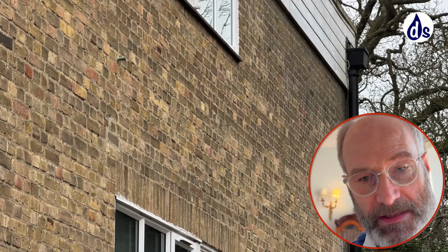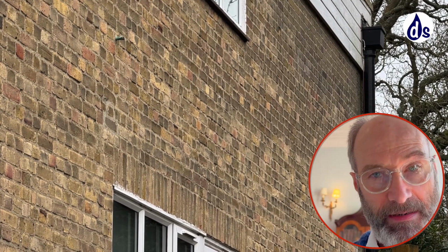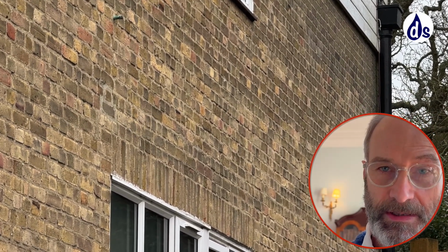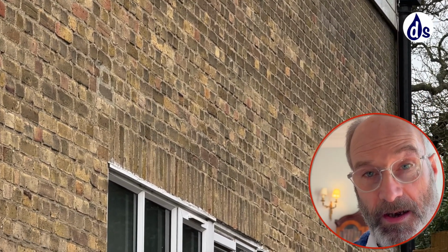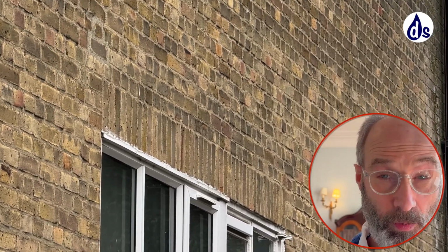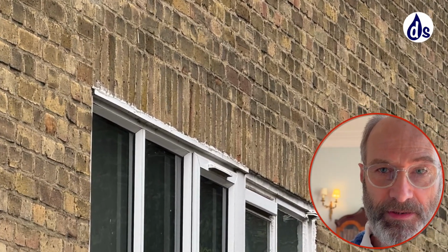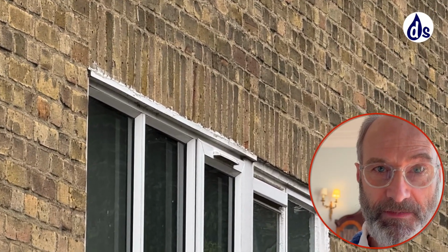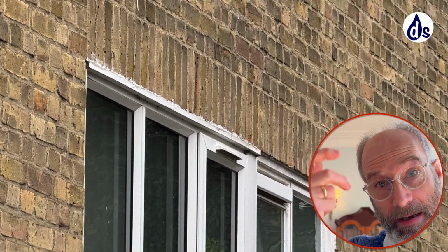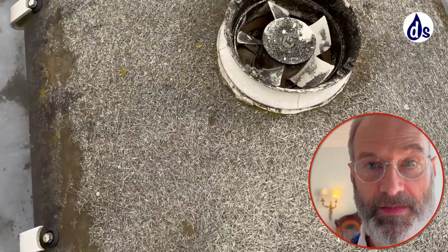The other thing in this property is there was very little ventilation. In fact, the whole building had very little ventilation. I think that's because there were crittall windows and probably hard to ventilate, and putting ducting through cavity walls is much harder. But I think you have to explore different ways of ventilating the property, including the original ducting system, getting that working again.